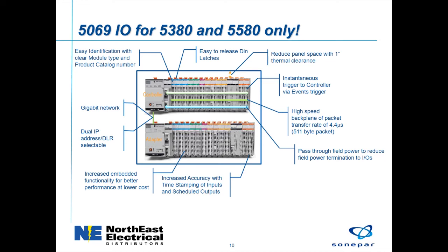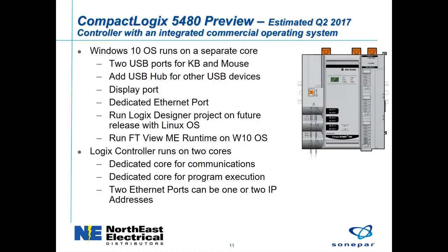There is a new CompactLogix 5480 controller. Estimated release is Q2 2017. This is going to be the first controller that actually offers a Windows 10 operating system itself. So this is a 4-core chip, and one of the cores will run Windows 10. Along with Windows 10, or I should say on the Windows 10 side of it, it'll have 2 USB ports for things like a keyboard and a mouse. If you need more than that, you'll have to add a USB hub. It has a DisplayPort output to run to your operator interface screen. It has its own dedicated Ethernet port.